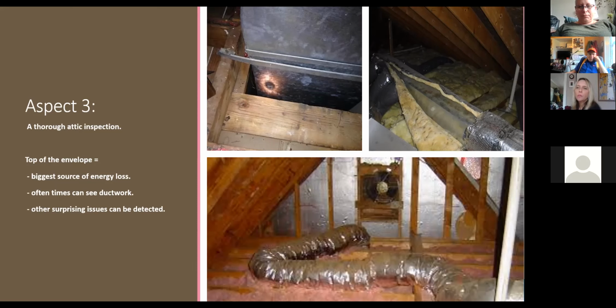The picture on the top right shows a supply duct whose insulation has been split. Not only is that an energy loss issue, it impacts comfort in whatever room this ductwork serves, and again it could be a condensation issue - if you have hot or cold air in that duct and the attic is the exact opposite, with a 60-degree temperature difference, you could end up with mold.